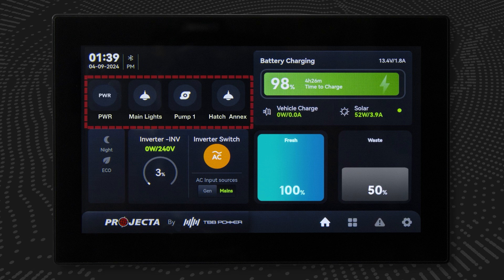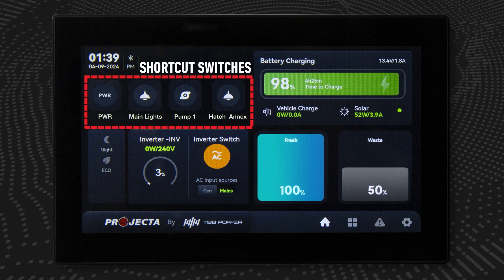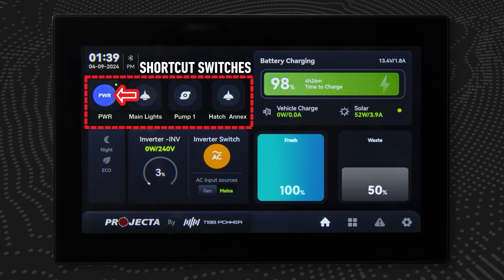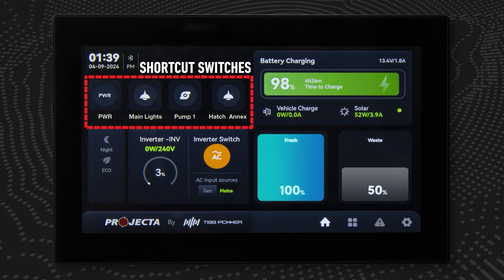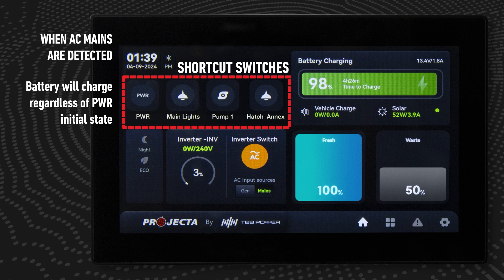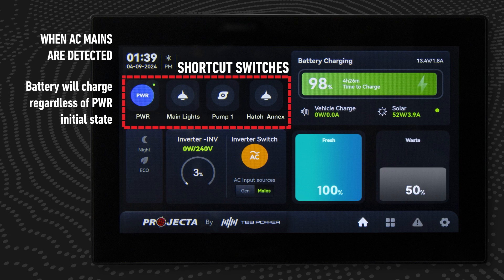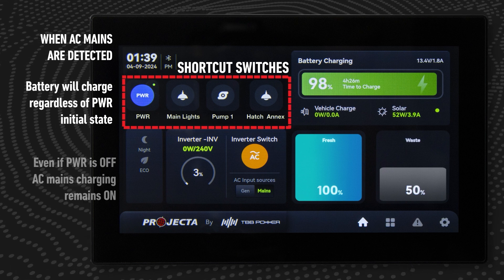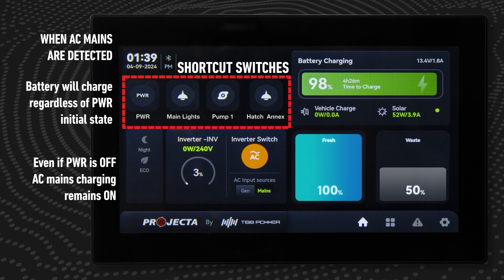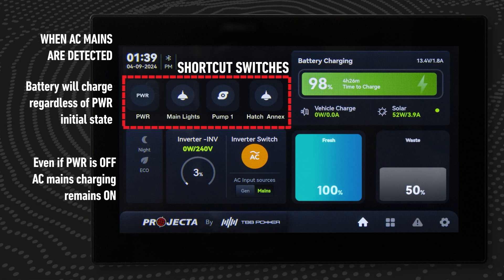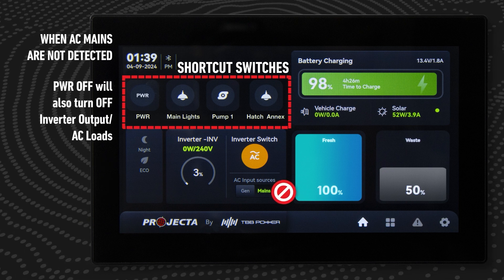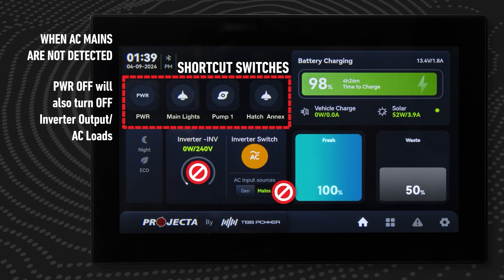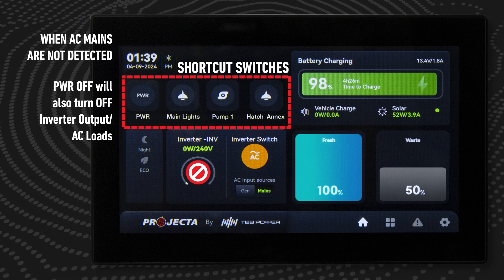This region contains shortcut switches for some of the system's most common functions. The power switch will turn on and off all DC outputs. Regardless of the initial state of power, once AC mains are detected the system will start charging the battery even if power is turned off — AC mains charging will remain on. If there is no AC mains detected, pressing power off will also turn off the inverter output, thus turning off the AC loads.